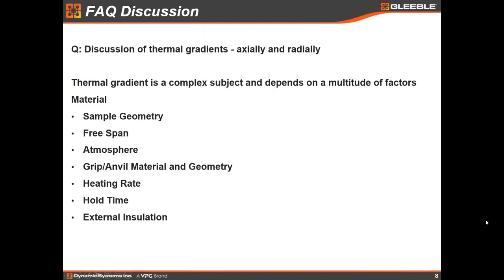There were a number of questions throughout the webinars about thermal gradients, so I asked Brian to put together a couple of slides to talk about thermal gradients in general. Thermal gradients is a pretty complex topic in the Gleeble. In the Gleeble, the thermal gradient is actually a design feature — the initial Gleeble was designed to do heat-affected zone testing and simulation where a thermal gradient is exactly what you want. Some kinds of testing you want a high thermal gradient; some kinds, you want a low thermal gradient. With different grips available in the Gleeble, you can control the thermal gradient.